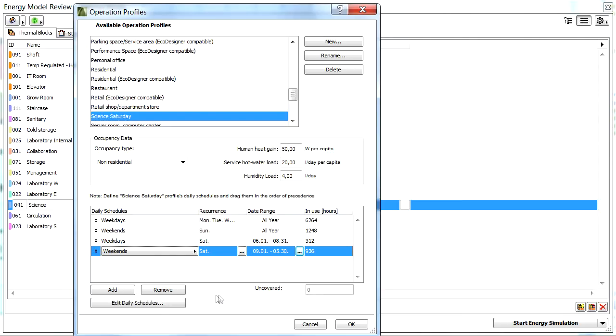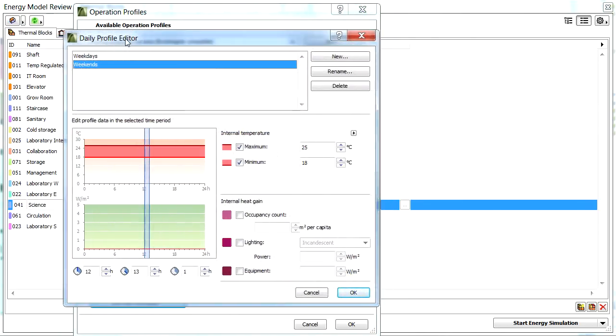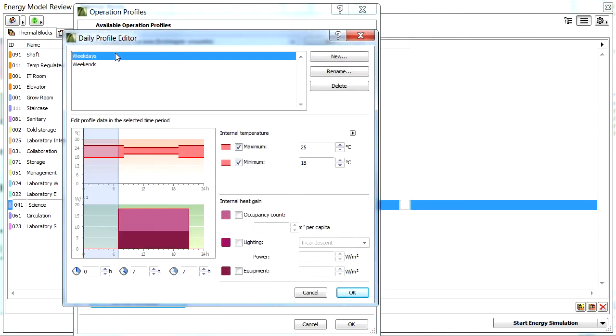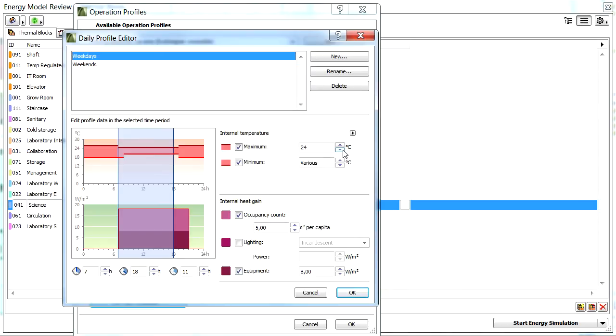Let's proceed and adjust the daily schedule for the new profile at the Daily Profile Editor dialog. We will define workdays from 7 a.m. until 6 p.m. The maximum internal temperature will be 24 degrees Celsius, and the minimum internal temperature will be 20 degrees Celsius.